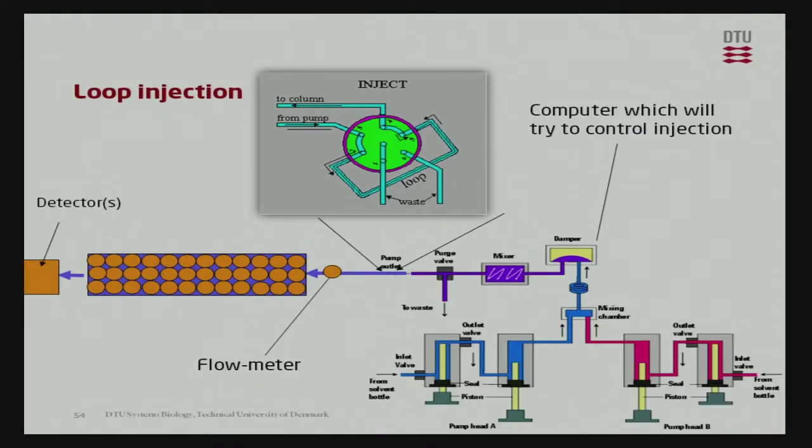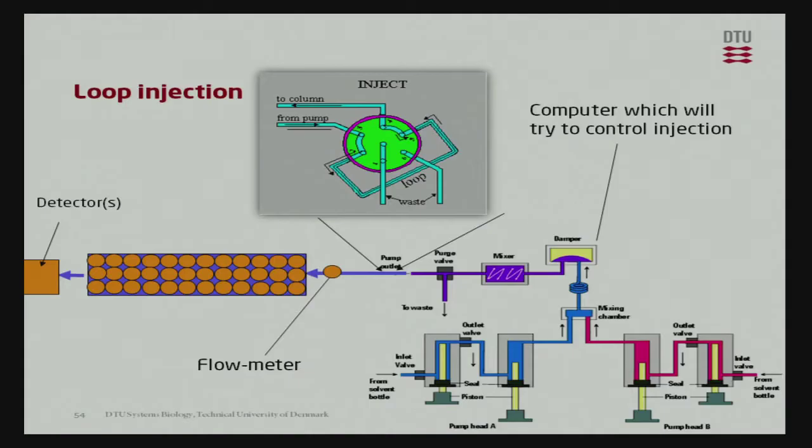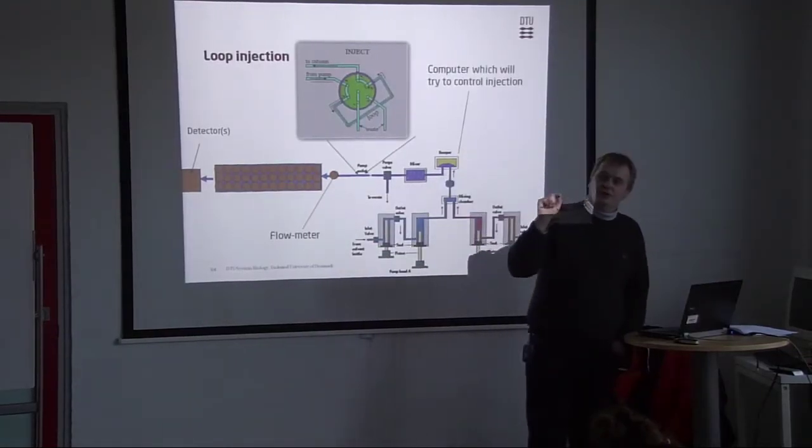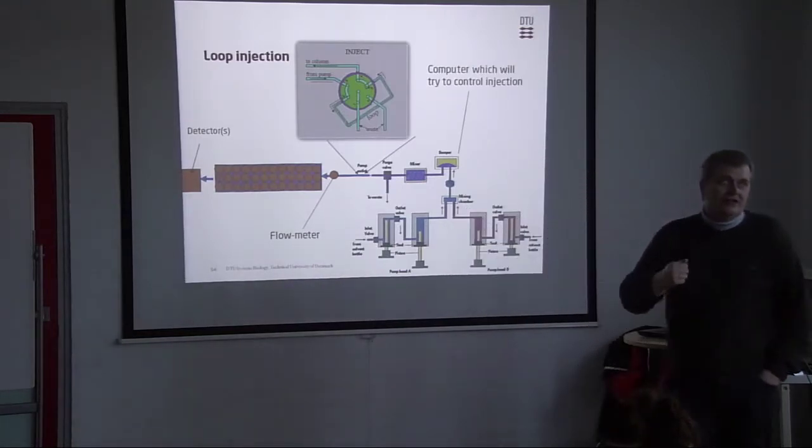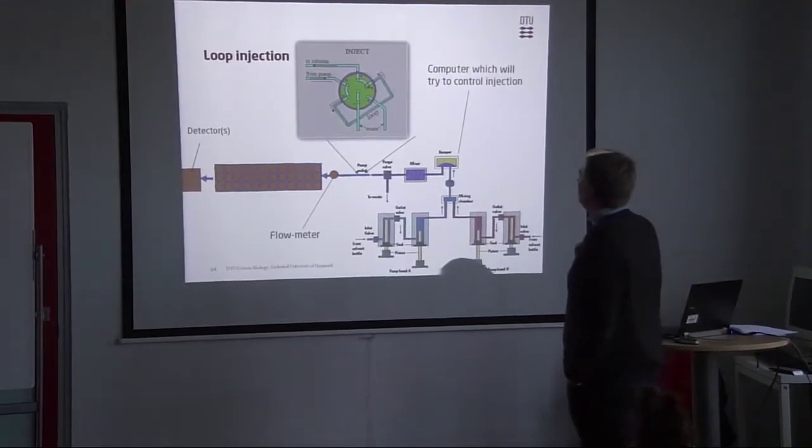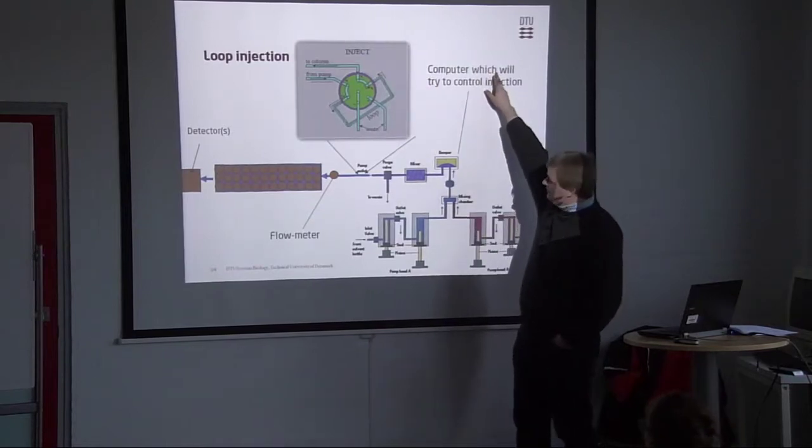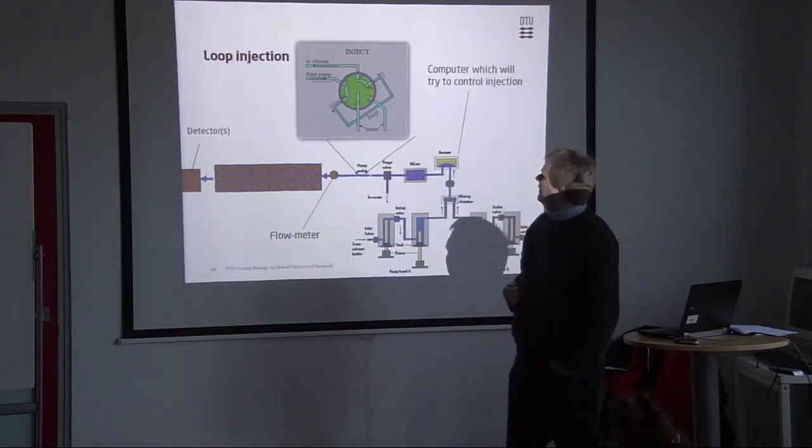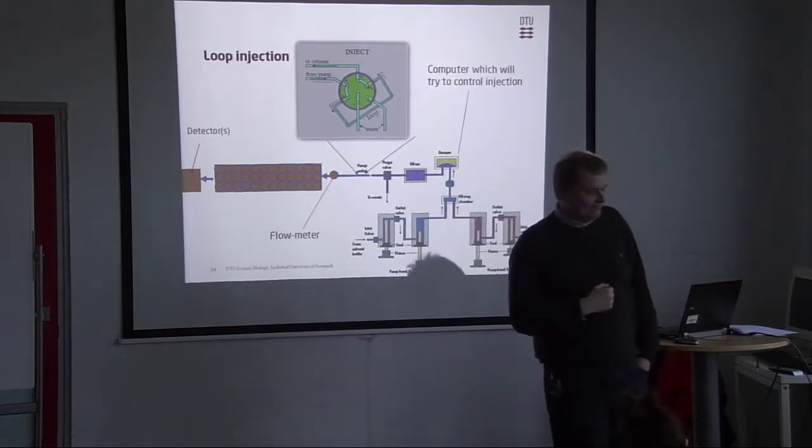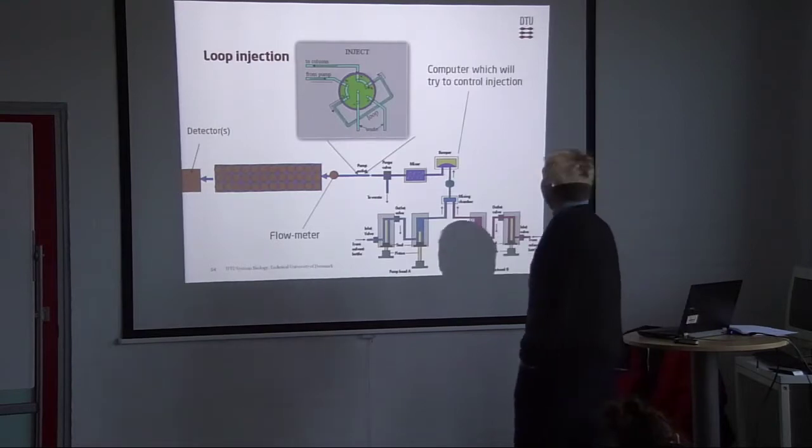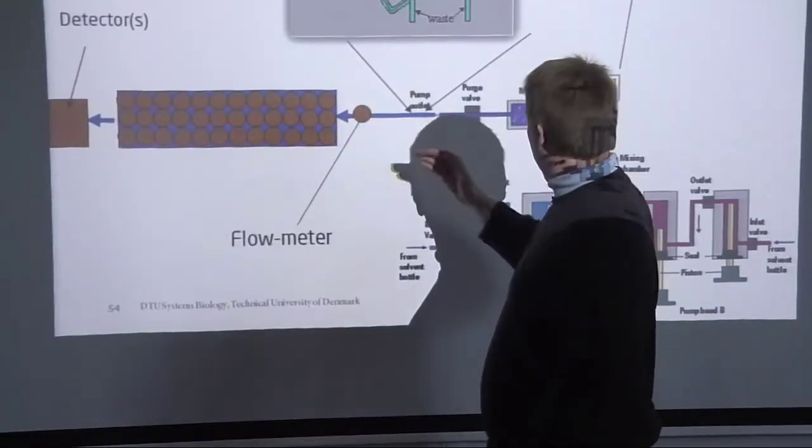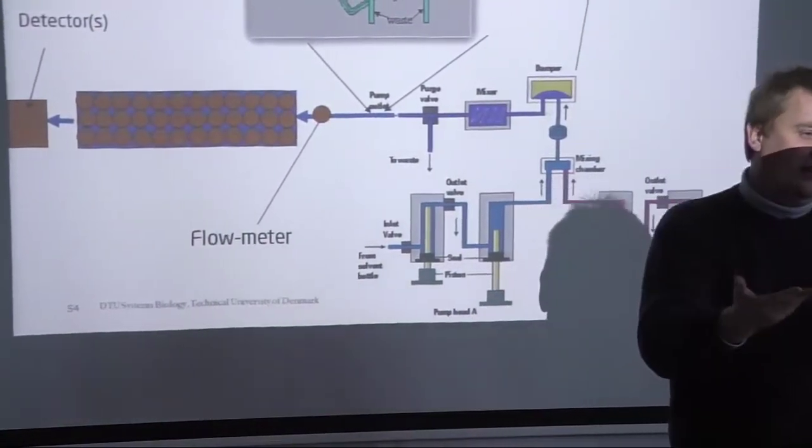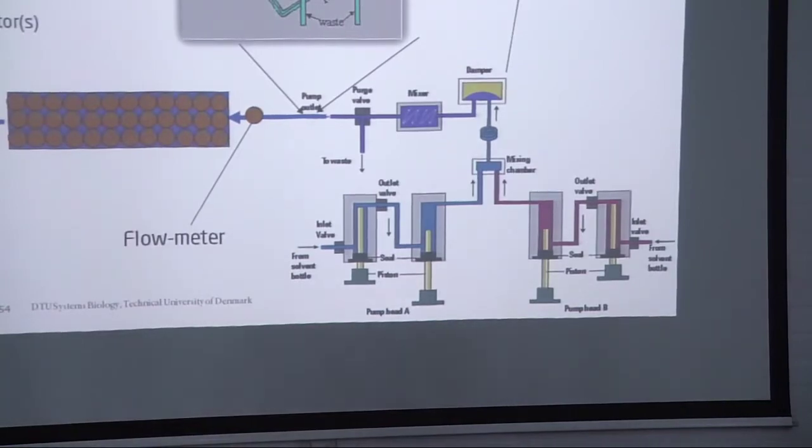So, a slightly more detailed HPLC system, and what you should recall is that all HPLC systems are computer controlled, and in general, most of them have a flow meter. So you type in, into the computer software, I want, let's say, 1 milliliter a minute, 0.1 milliliter a minute, that you type into the software. The flow meter will then actually give a reading to the computer, and if the flow is too low, it will increase the pressure of the pumps.